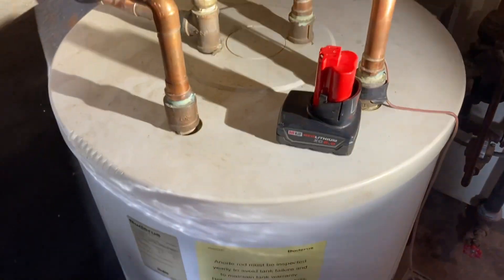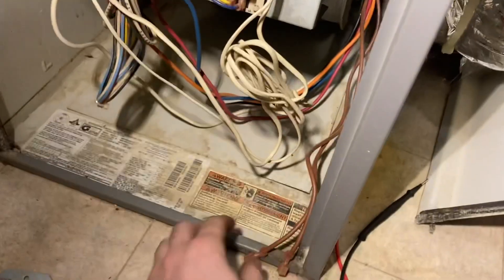The customer went from having to spend a lot of money - she called us out to get a second opinion, and we just saved her a lot of money. Got called for a furnace noise, did not find a furnace noise, but we did find a bad run capacitor - or start capacitor, whatever you call it.